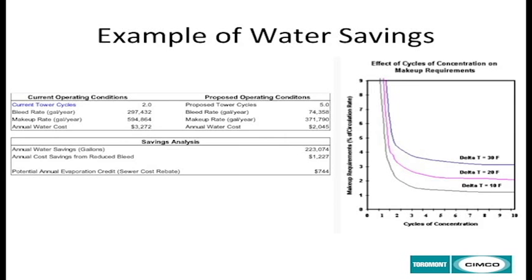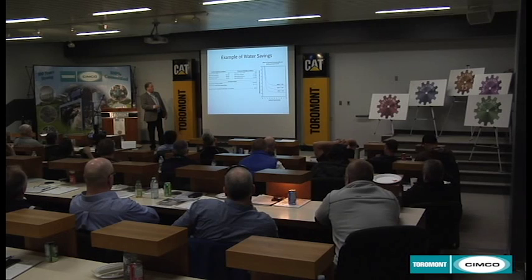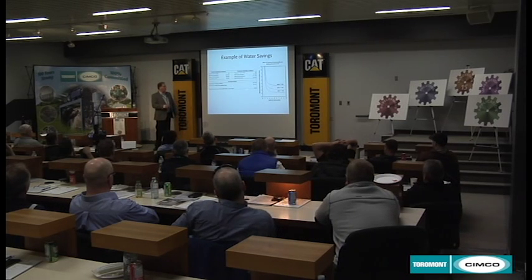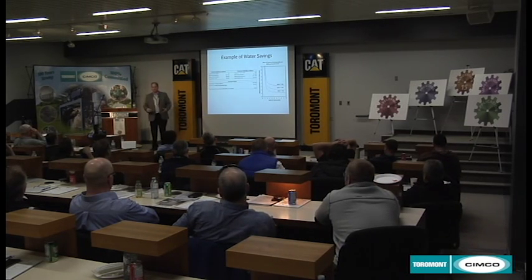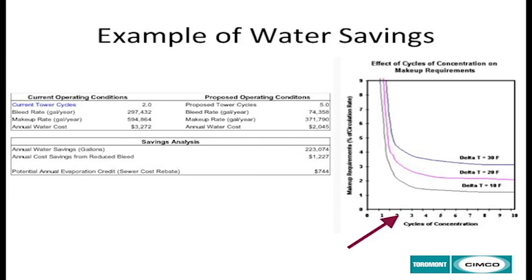So if you look at the numbers of what we're looking at, the water cost is not a lot, but the amount of water is the important thing that we have to look at. So here's an example of what water savings occur. If you're running 2 cycles, you could see there's a lot of water wastage. If you run 3 cycles, then as you progress, I always use 5 or 6 cycles of concentration as my optimum cycles of concentration, depending on the area you work in, which area you are at.